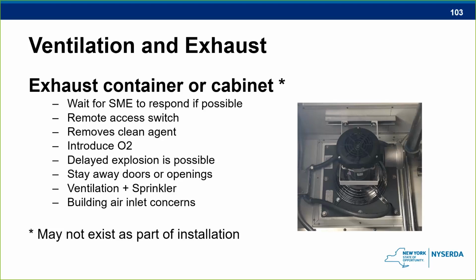In New York City, we have seen that. We've seen dual agents. We've seen a clean agent, but New York City said you still want some sort of water going on the inside. And what they did is they put in that dry pipe where the engine would just come in and dump their water right through the dry pipe and into the actual enclosure, where the firefighter would never have to get involved and they wouldn't make entry into it. There was always a concern that the firefighters would actually put water in there unnecessarily.